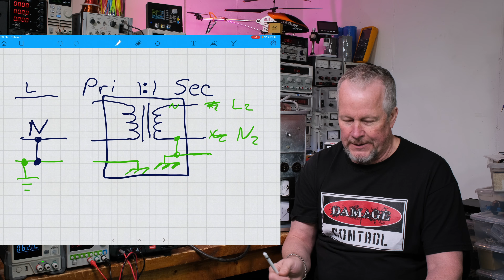But most often when you think about an isolation transformer, you think about having a floating output that's not referenced to your ground system. And that way, if one of the wires or the other wire touches it, then it's okay, if it does it by accident, or if you touch it by accident. So if you're touching this and then touch your chassis.